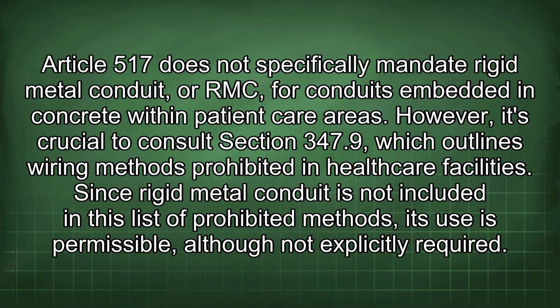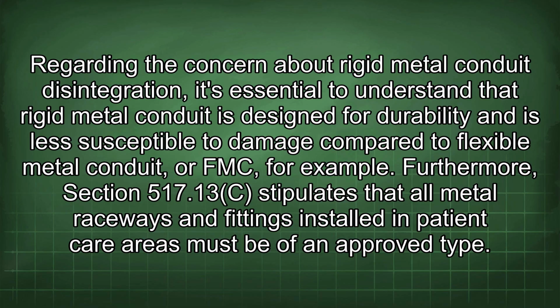Article 517 does not specifically mandate rigid metal conduit, or RMC, for conduits embedded in concrete within patient care areas. However, it's crucial to consult Section 347.9, which outlines wiring methods prohibited in healthcare facilities. Since rigid metal conduit is not included in this list of prohibited methods, its use is permissible, although not explicitly required. Regarding the concern about rigid metal conduit disintegration, it's essential to understand that rigid metal conduit is designed for durability and is less susceptible to damage compared to flexible metal conduit, or FMC, for example.